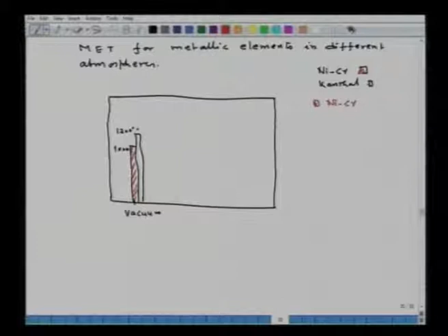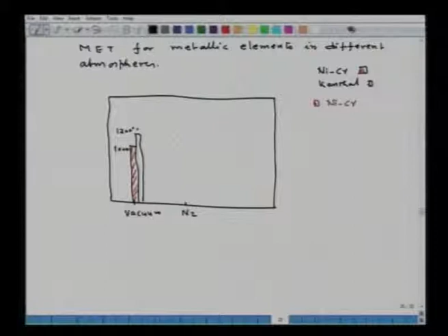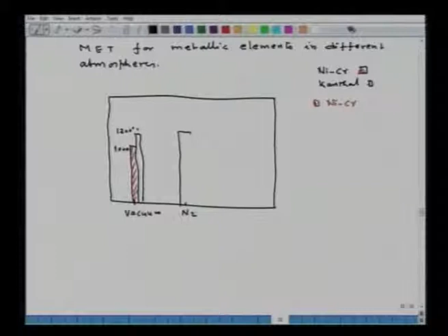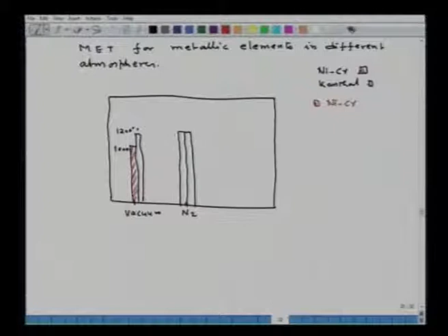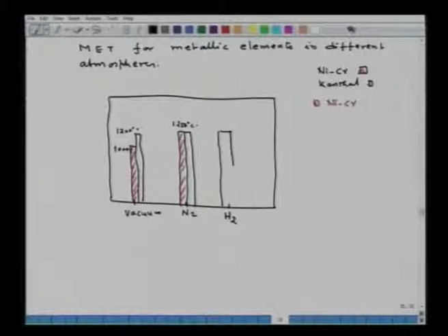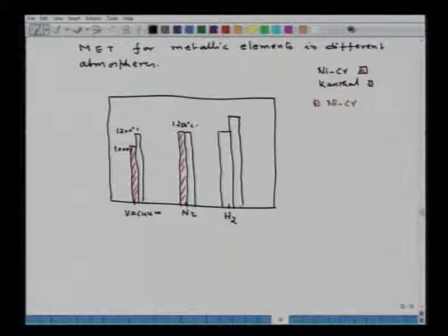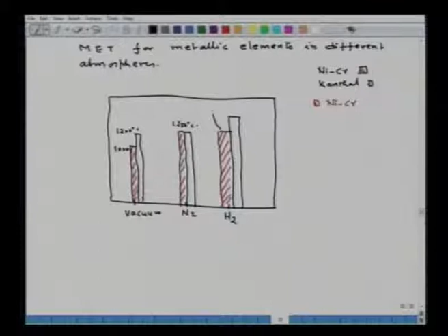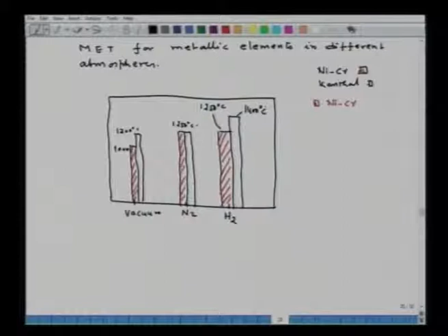Now, similarly, if I take a nitrogen atmosphere, for nitrogen atmosphere both the elements can be used safely up to 1200 degrees Celsius. This is again nickel chrome, and this temperature is 1250 degrees Celsius. If I take a hydrogen atmosphere, then this is for the nickel chrome, with a temperature of 1250 degrees Celsius, and this is for the kanthal, which can be safely used up to 1400 degrees Celsius. Similarly, the response of other elements can also be determined in order to select a heating element for a particular application.